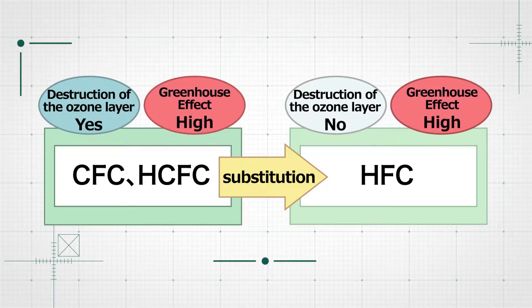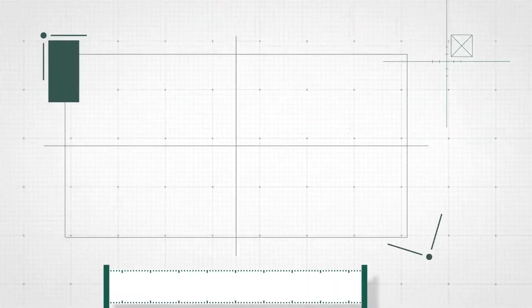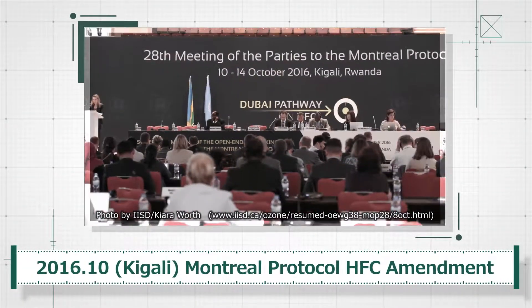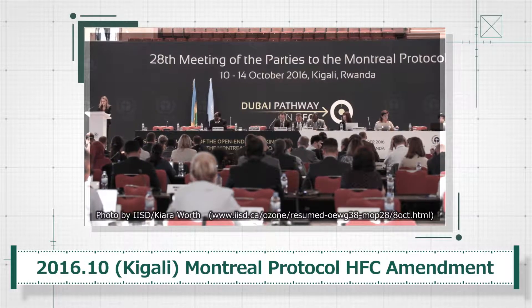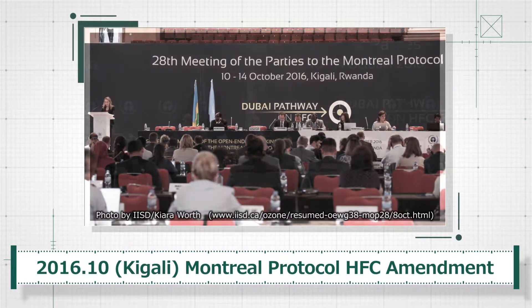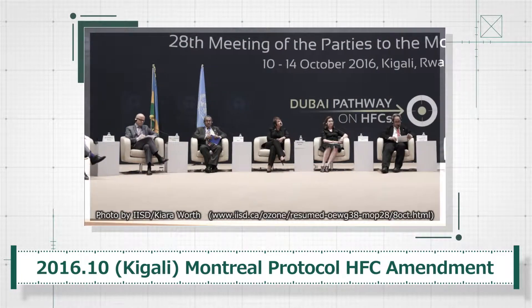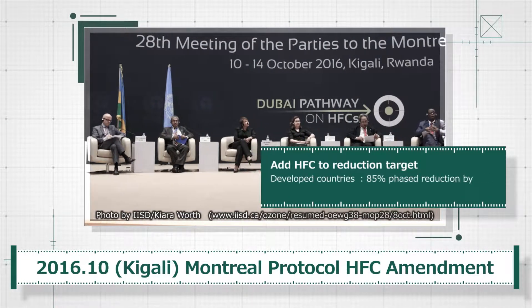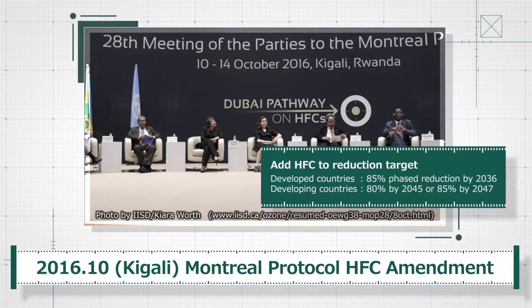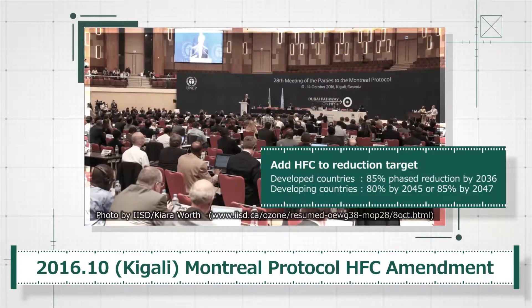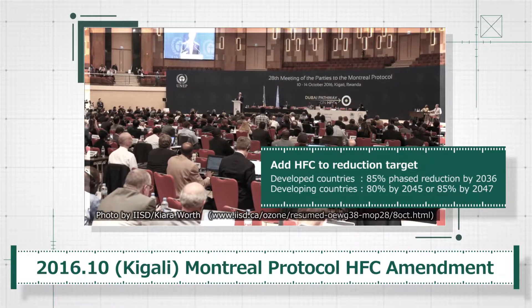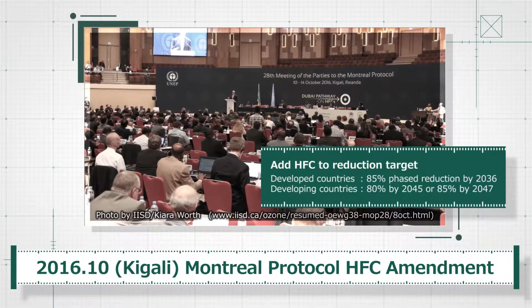From the viewpoint of measures against global warming, it became necessary to suppress HFC emissions into the atmosphere. Therefore, adding HFC to the reduction targets of the Montreal Protocol was discussed internationally, and an agreement was reached in Kigali, Rwanda in October 2016. Developed countries are required to reduce HFC by 85% by 2036, and developing countries by 80% by 2045 or 85% by 2047.